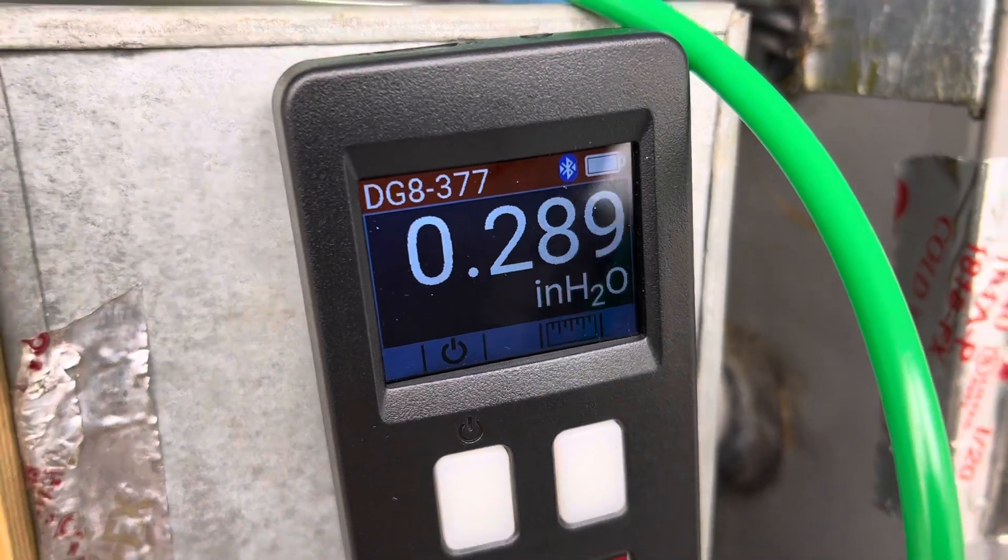We're basically right at 288 and 290 with the dirty filters in there. This is not even taped off yet, I'm still leaking air around here. So let's take that out. 288-290 is our number, we're looking for improvement.